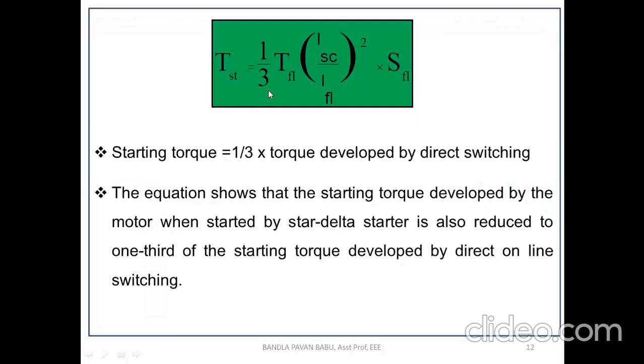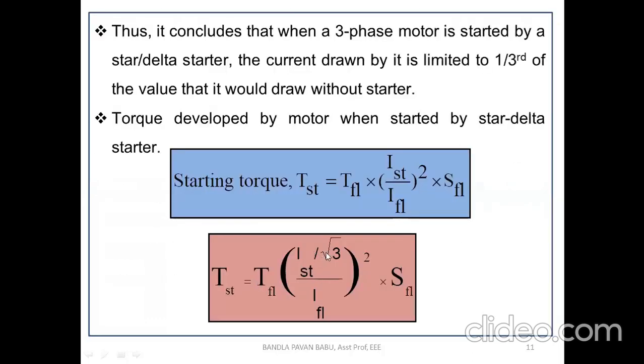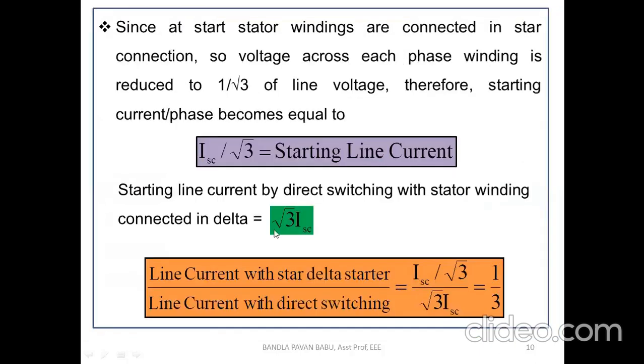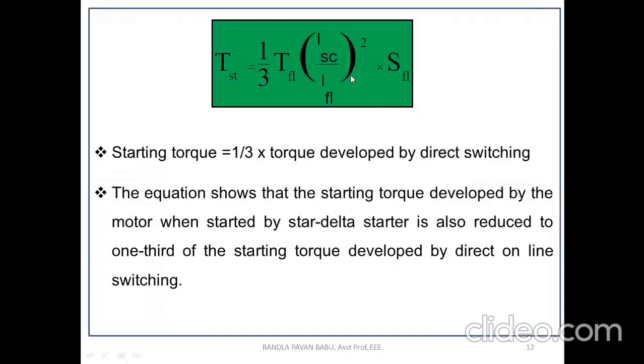So TST equal to 1 by 3, so the root gets cancelled here, it becomes 1 by 3 TFL times (ISC by IFL) whole square into SFL. So what is IST here? This is IST, the starting line current, that is ISC by root 3. So it is (ISC by IFL) whole square into SFL. Again here TST is the starting torque, TFL is the full load torque, ISC is the short circuit current, IFL is the full load current, and SFL is the full load slip.